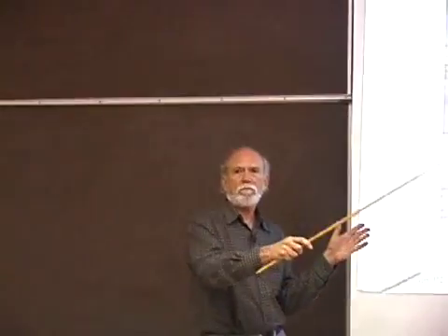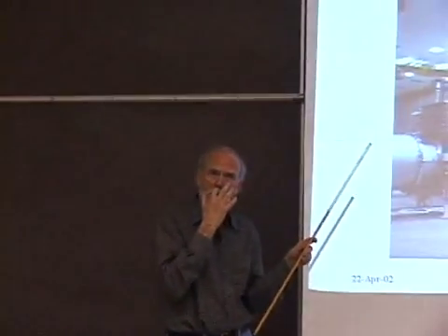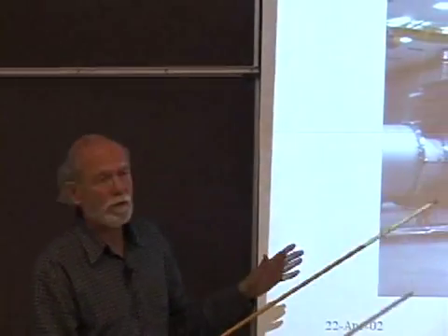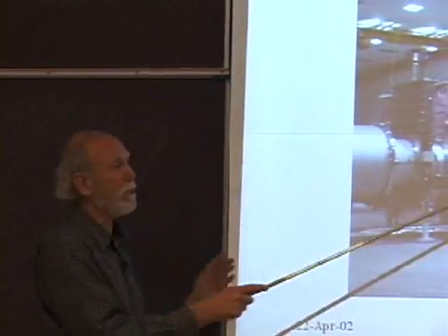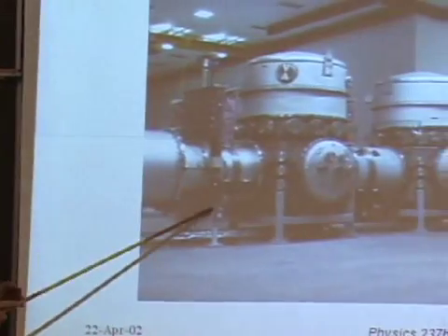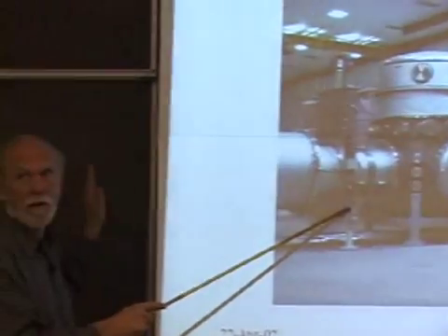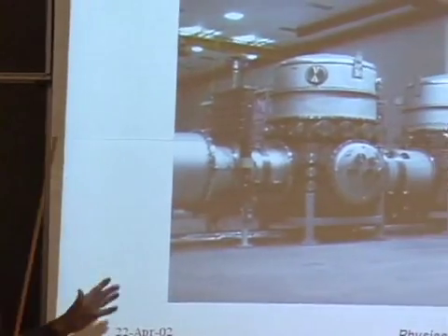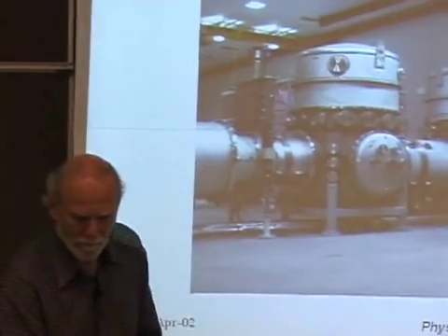So once we make the long vacuum, which works at 10 to the minus 9 torr, we never change that. That stays baked out. If we want to work on a mirror or something in here, you close these gate valves, keep the long arms under high vacuum, and go inside the chamber and work on it. It all has to be done clean, but that's the scheme.